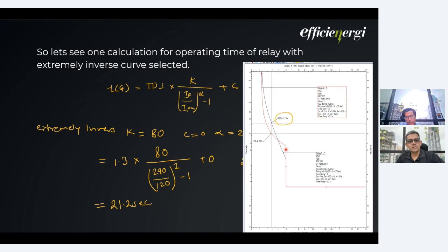basically you can see these two curves. These two curves have been set to the same values. The pickup is the same, the TDS, the time dial setting, is the same, everything is the same. But one has the extremely inverse characteristic and one has the standard characteristic. You can see that for 290 ampere, one is tripping faster than the other. The standard inverse trips at a lower time, 10.2 seconds, whereas the extremely inverse trips at 21.5 seconds.